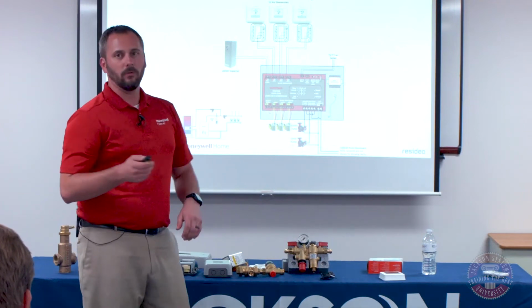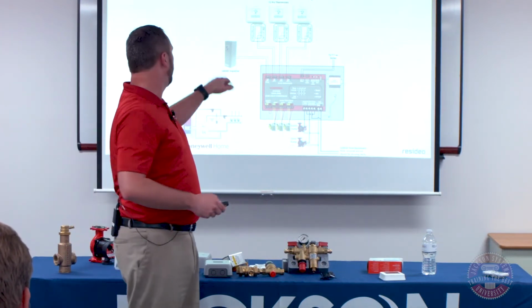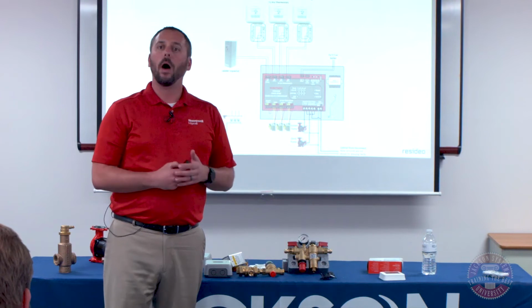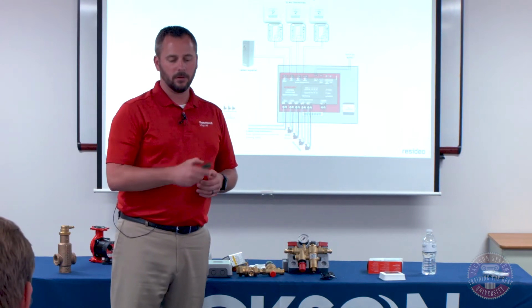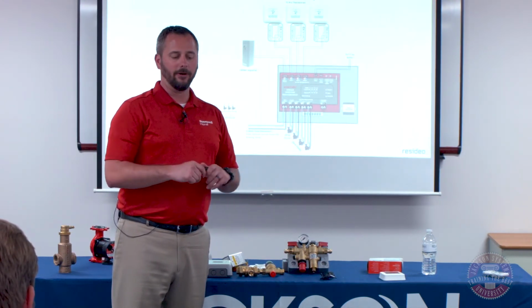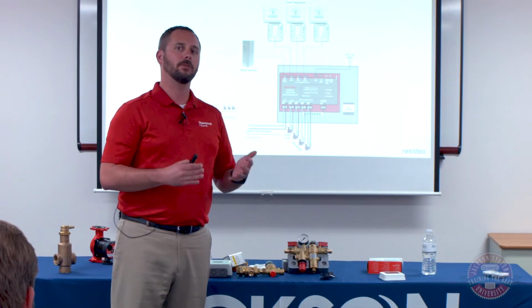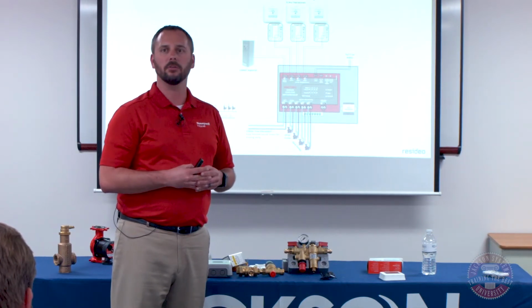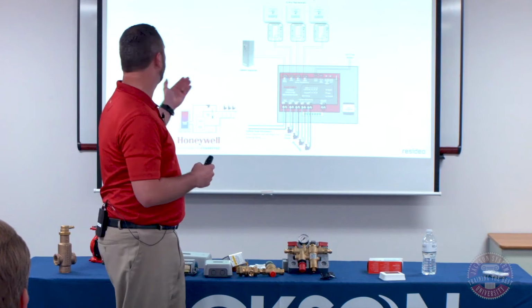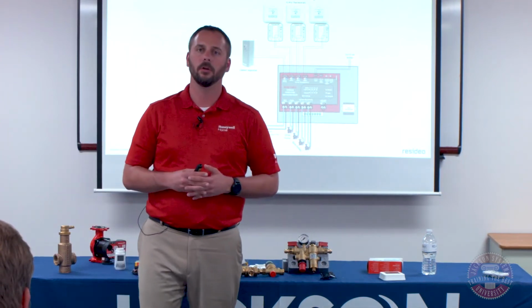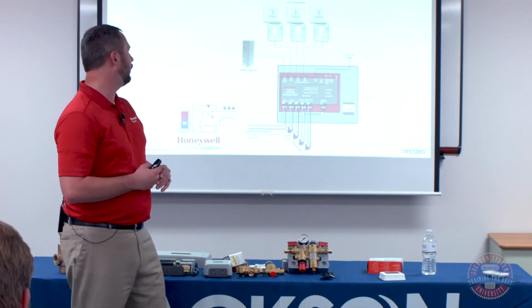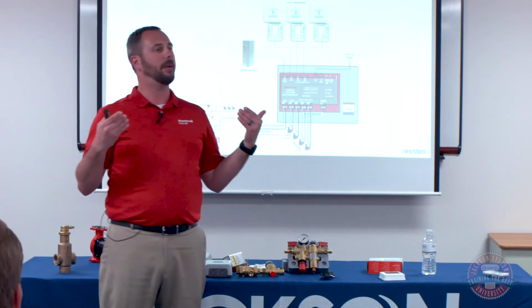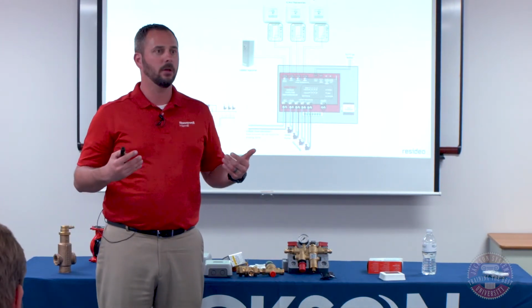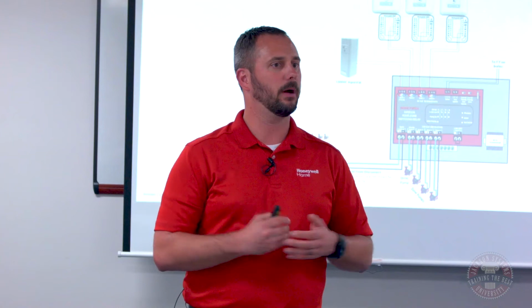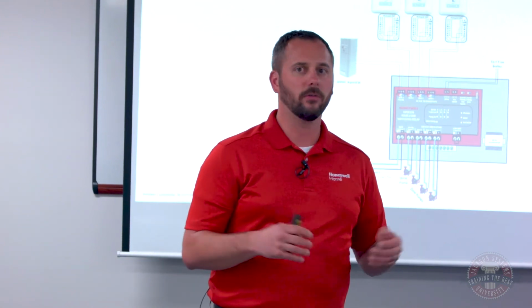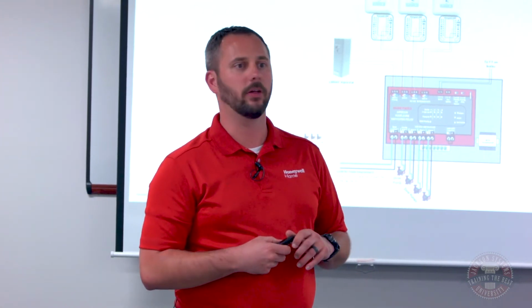So we talked about zone valves and zone pumps. This example that I'm showing you up here is typical wiring for a zone valve system. This wiring here, basically the exact same configuration, but instead of valves, now we're using zone pumps. So you lose the system pump and you add the zone pumps. You see the wiring is still incredibly simplistic. The top of that panel still gets wired exactly the same. The only difference is instead of valves, now we're using pumps at the bottom. So 14 or 12 gauge wire hooked into the circulators.